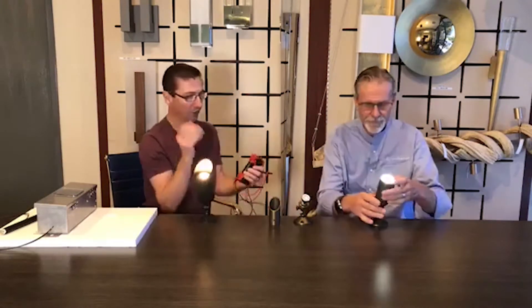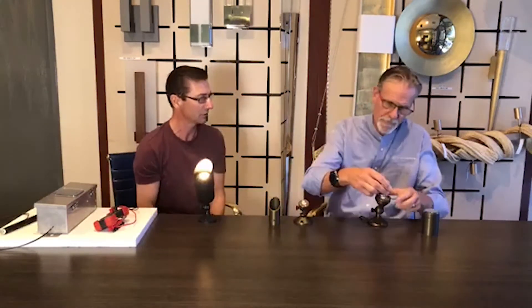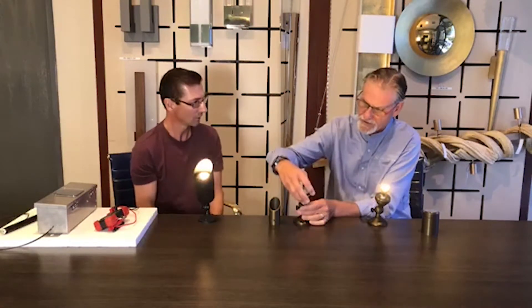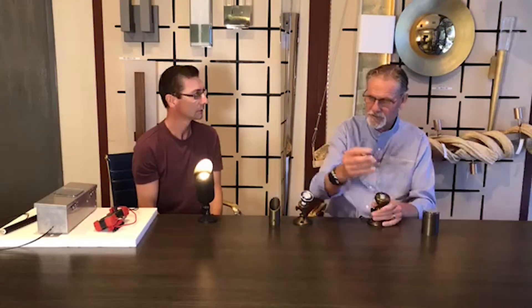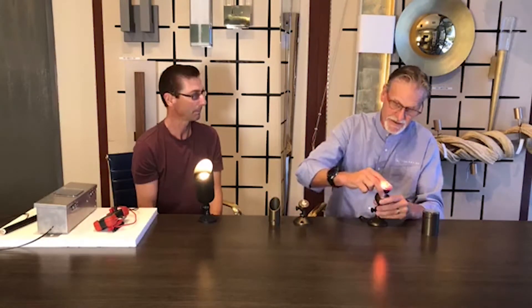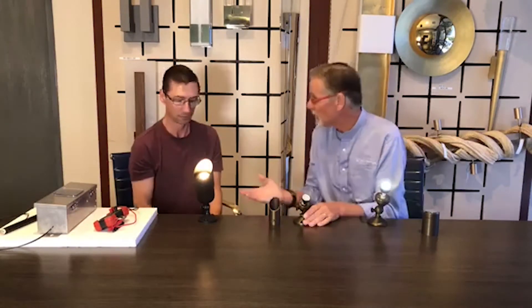I'll get this phone call all the time. I switched out the bulbs, and one worked when I put it in a different fixture. They'll call and say your fixture's bad because they've swapped the bulbs and the bulbs are working right. But there's something wrong with your system or something wrong with your fixture. So the first thing I'm going to do is pull up the multimeter.